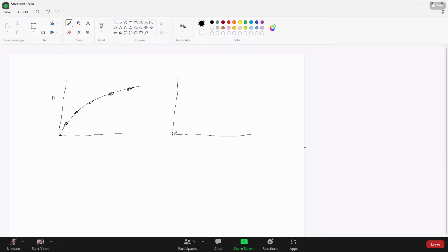So that you have, when you do this, a nearly linearity. And then you can correct with 2 points, or if you have a rest of non-linearity inside, you can take a third point, so that you make the line approximation with less points.